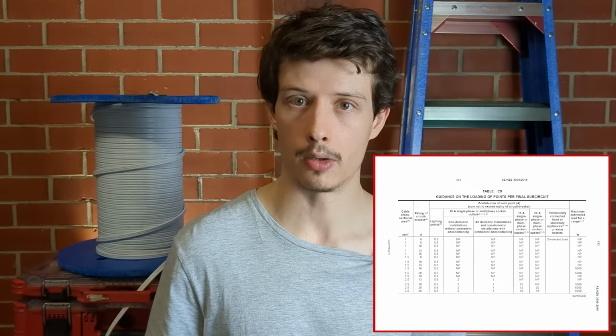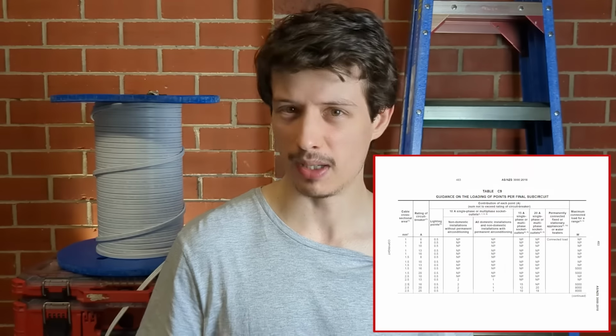It states that any circuit that's rated on a 32 amp circuit breaker or lower needs to be RCD protected. If these are usually protected by 16 or 20 amp breakers, then we're going to be putting an RCD on them. The minimum cable size for these socket outlets is 2.5 mil, 2 core and earth, TPS. This is the most used type of cable we have for socket outlets.